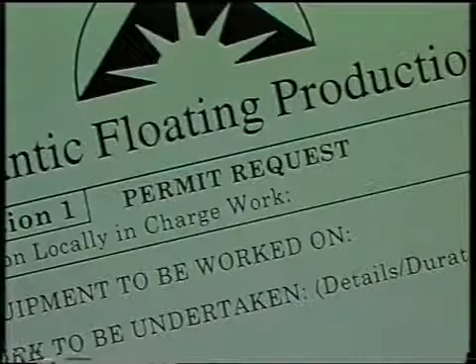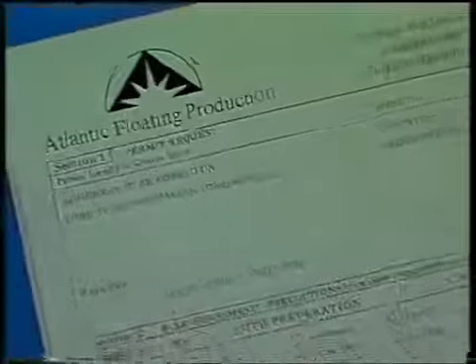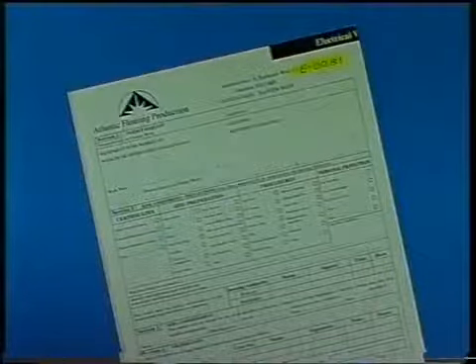High voltage operation necessitates extremely rigorous safety procedures which you cannot ignore. When investigating any fault or when doing routine maintenance, it is essential that the correct documentation is filled out and countersigned. For instance, good practice would require the Chief Electrotechnical Officer, or CETO, to fill out a permit to work order for a routine insulation test on a high voltage circuit.